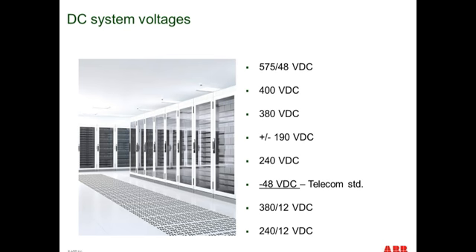Over time, the industry seems to have coalesced around a number of voltages that seem to be used interchangeably. So today you'll see what's referred to as high voltage DC in data centers, spoken about in terms of 400 volts DC, 380 volts DC, and or plus or minus 190 volts DC. You'll also see a plus or a minus in front of the 400 or 380, indicating a positively or negatively grounded system, which is vastly different than the plus minus 190 volt DC, which indicates a midpoint grounded system. The purpose and interest behind the midpoint grounded system is that the voltage to ground is half that of a 380 or 400 volt system.